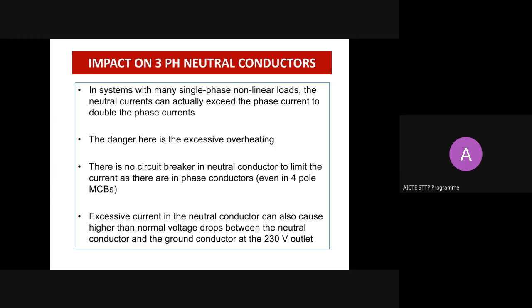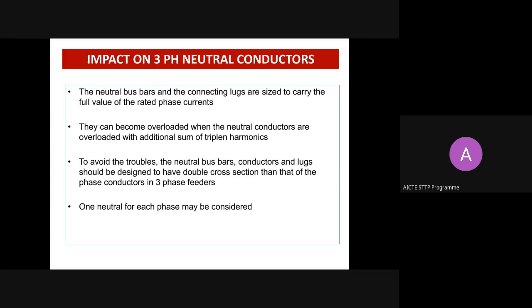Excessive current in the neutral conductor can also cause higher than normal voltage drops between the neutral conductor and the ground conductor at the 230 outlet. Here the problem is that the neutral bus bars and connecting lugs are sized to carry the full value of the rated phase current, because normally the neutral current is minimal when balanced without any harmonics. If it is unbalanced with lots of harmonics, the neutral current gets very high. That means the neutral conductor size should be matched with the phase current. If the neutral current is higher than the phase current, the conductor will naturally be affected. They can become overloaded when the neutral conductors carry the additional sum of triplen harmonics. To avoid this, the neutral bus bars, conductors and lugs should be designed with a double cross section. We have to oversize them to prevent such occurrences. That is a costly investment.